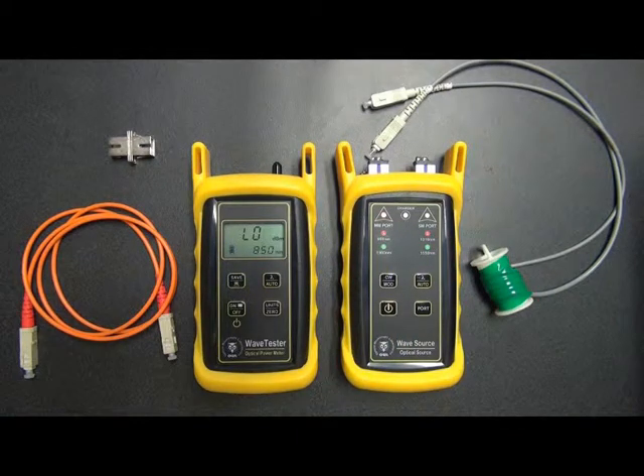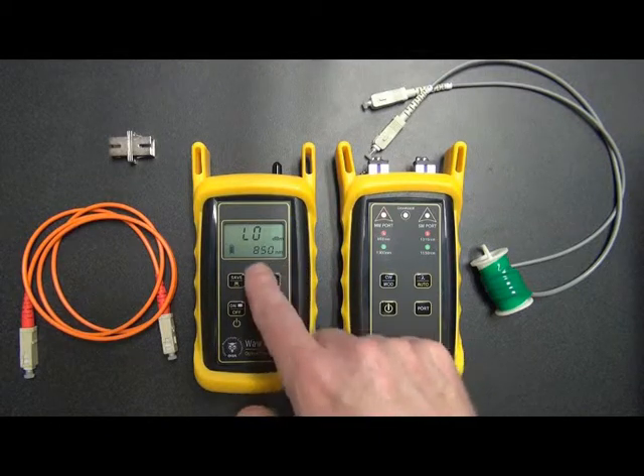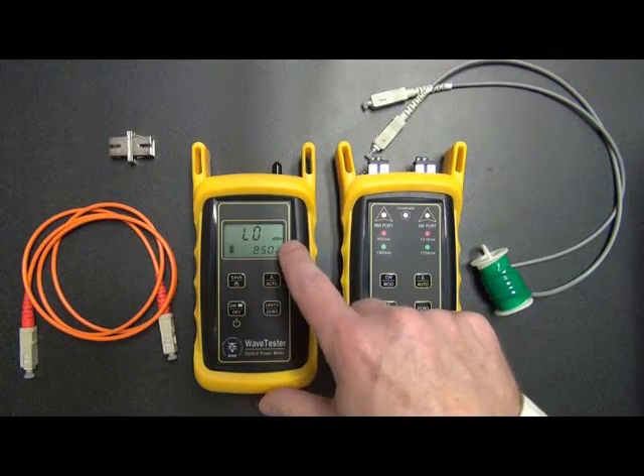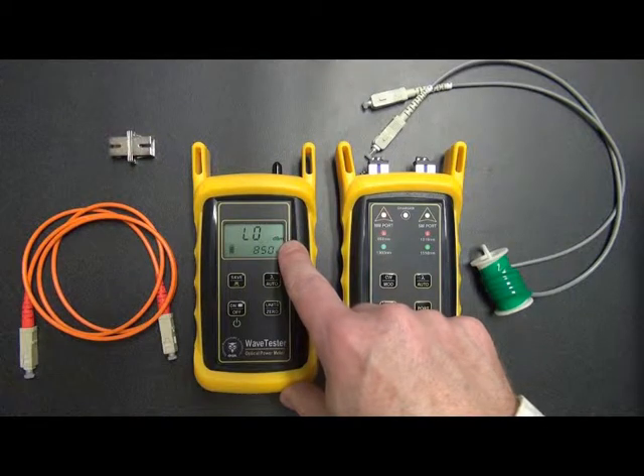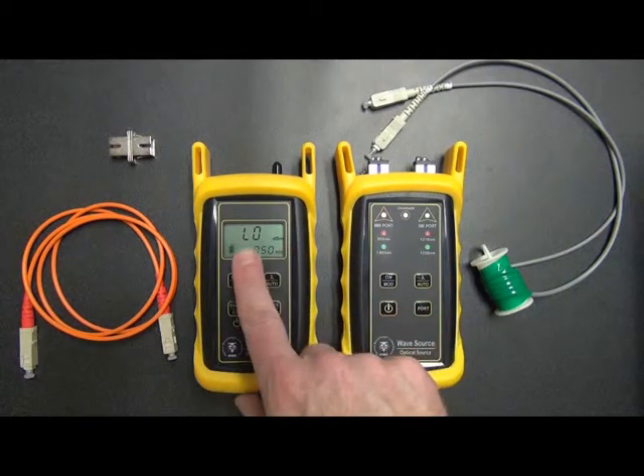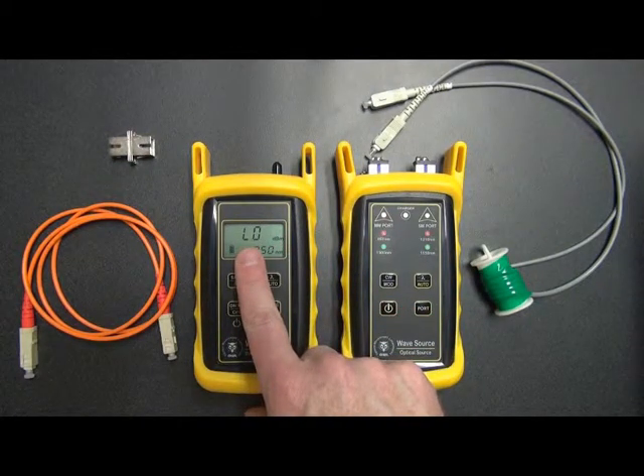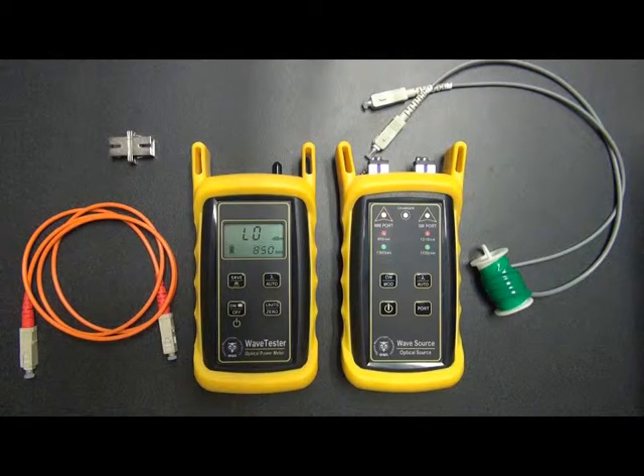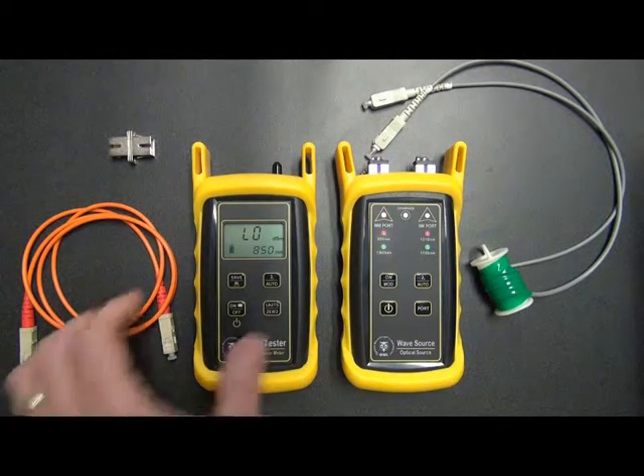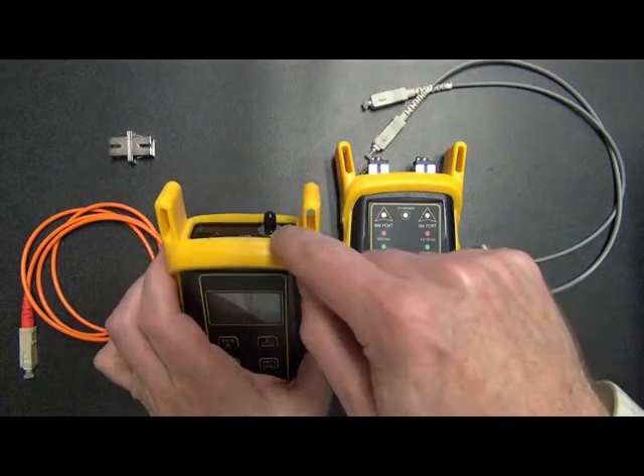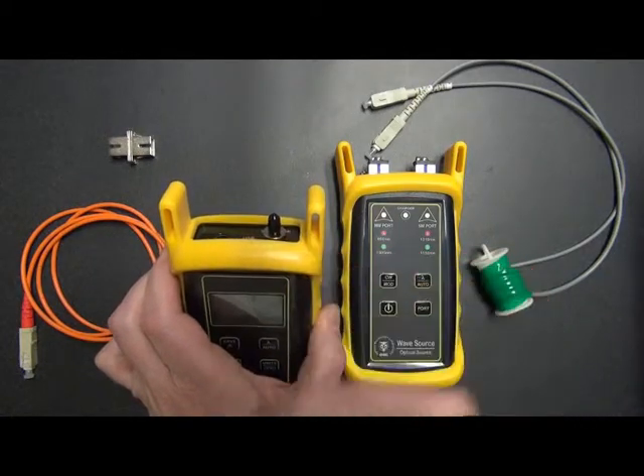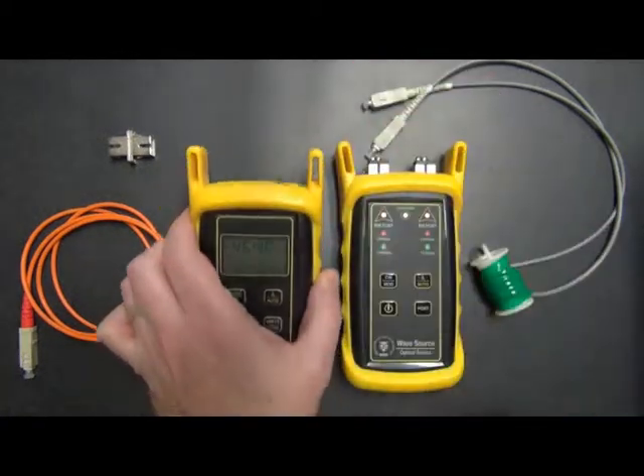Now on the WaveTester, we'll see a reading on the screen. We see that it shows 850 nanometers, and it also shows dBm, which is an absolute power measurement. However, we also see the word low. What low means is that there's no amount of measurable light coming into the photodetector. This is because the detector is covered by a dust cap. If we remove the dust cap, we will see that we get a reading.